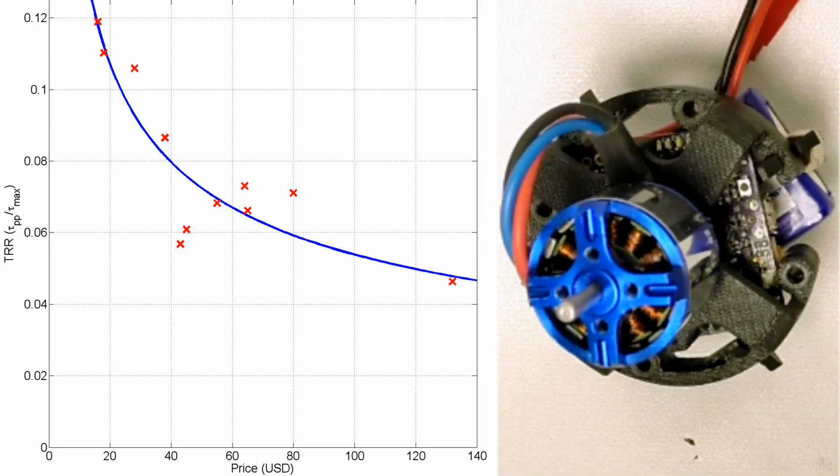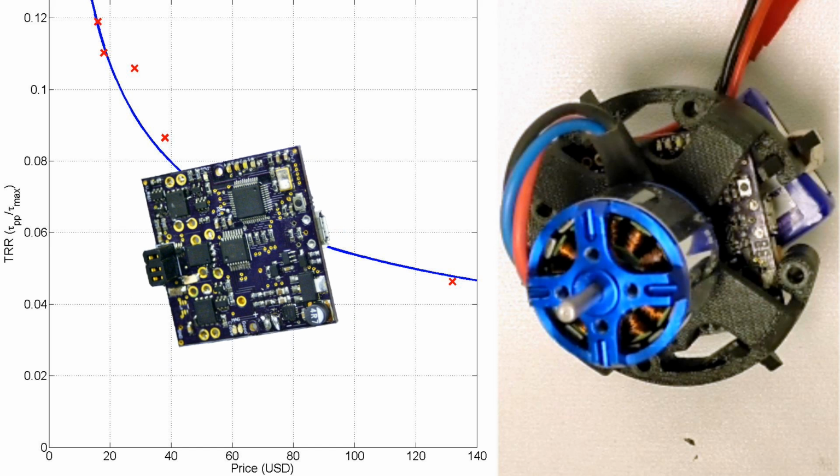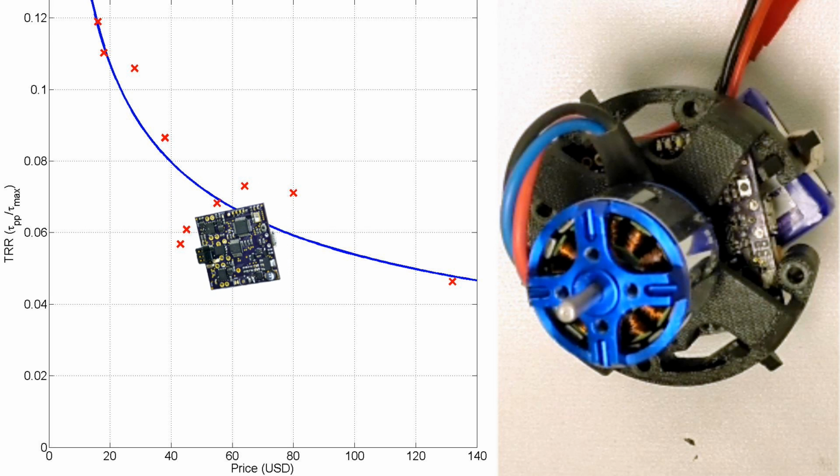Across a wide range of motors, torque ripple and cost are inversely related. Here, on the x-axis, we have cost. On the y-axis is the torque ripple ratio, which is a measure of torque ripple, and you can see cheaper motors have more torque ripple. In these applications, computation and electronics often hold a large portion of the cost, but with Moore's law and consumer electronics continuously driving down prices, actuators become the dominant cost, relatively speaking.